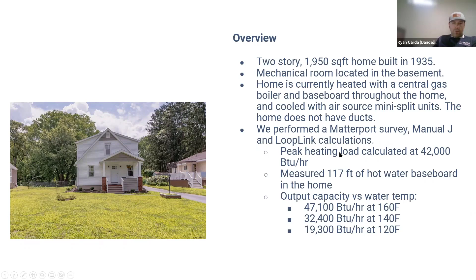The top one here is a high temp water-to-water unit capable of giving you 160-degree water to the space, but it's a cascading refrigerant system with 2 refrigerant circuits in series, so it can only operate in one direction - it can only operate in heat, it can't deliver AC mode. But we know with 160 degrees, that's what we need to meet the heating needs of the building on the cold day.